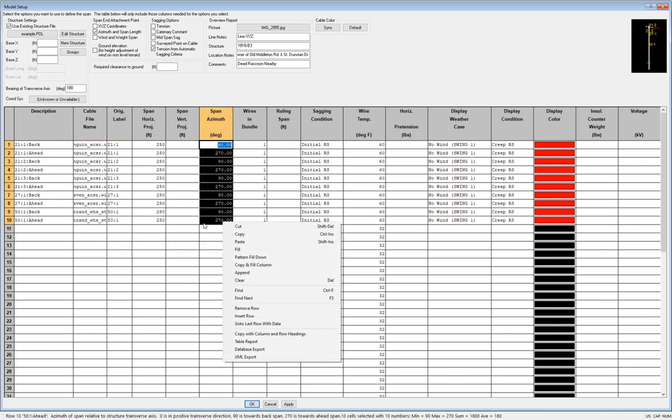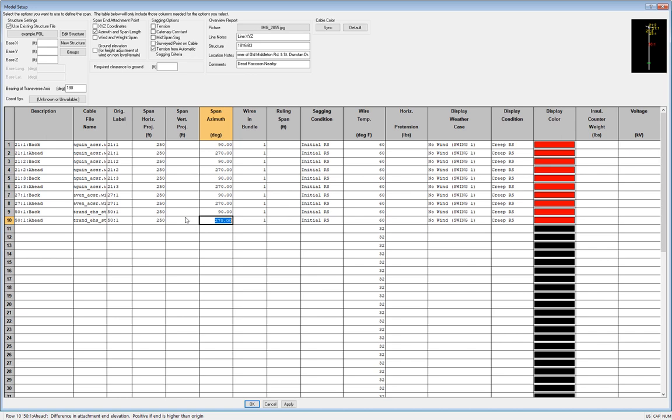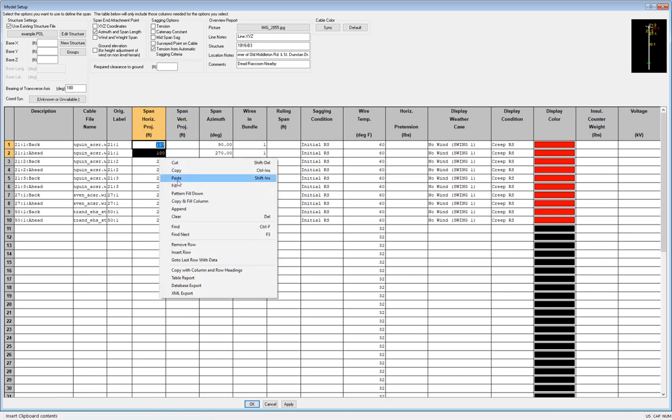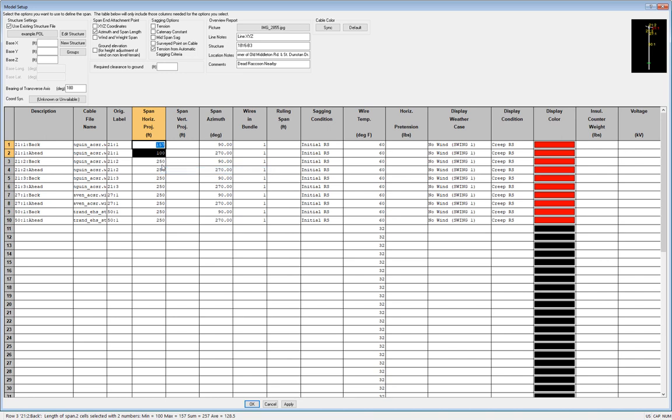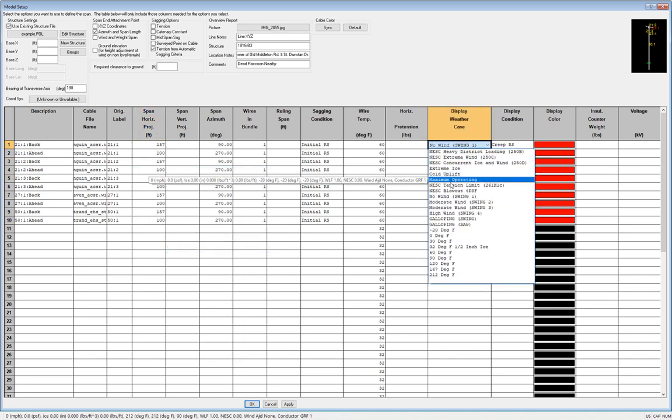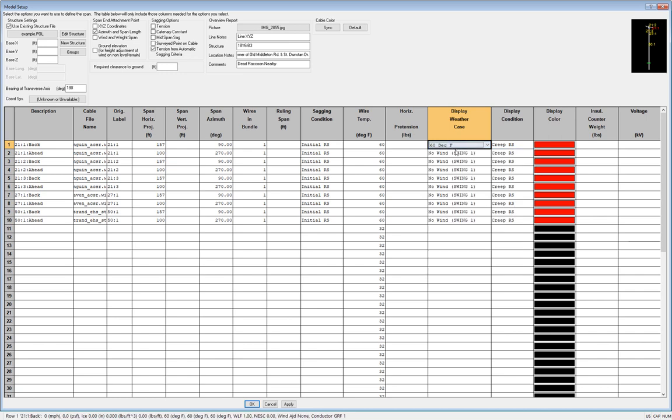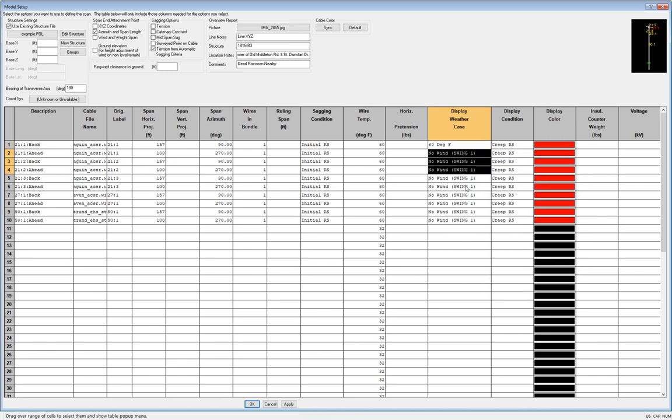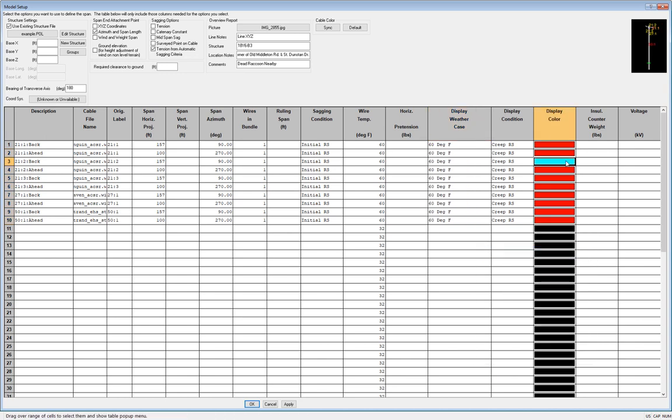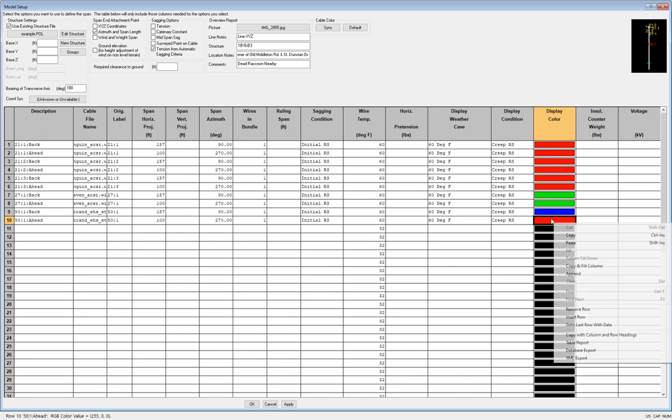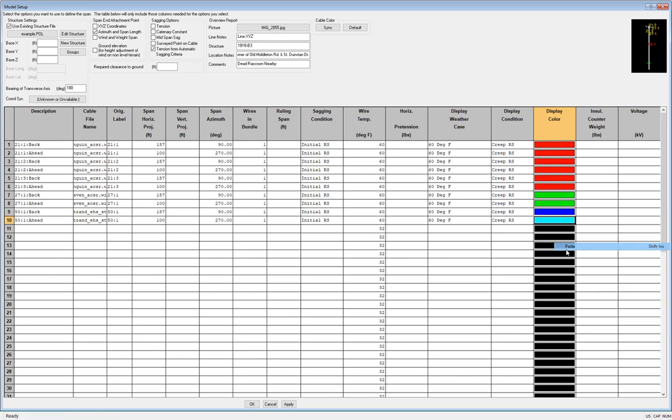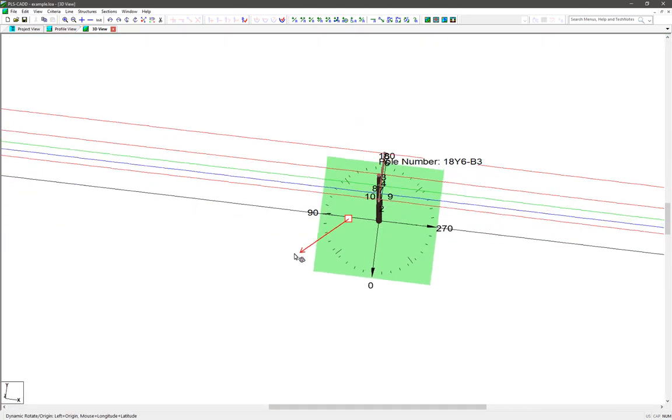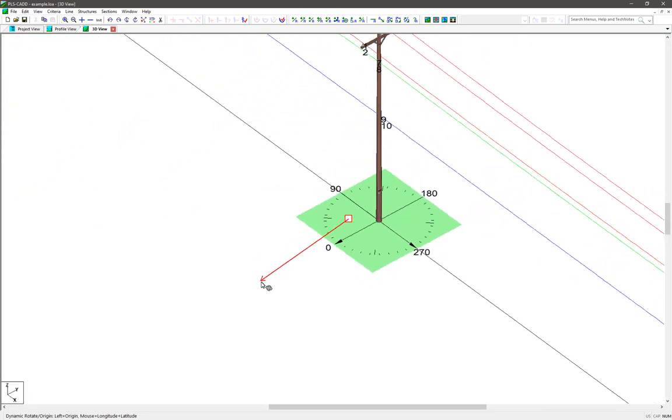The span azimuths, or wire direction, we don't need to make any changes to. The 270 degrees points to the head span, and the 90 degrees points to the back span. With this being a tangent structure, it doesn't need to be changed. We do, however, need to change our span lengths. The head span we measured to be about 100 feet, and the back span was about 157 feet. The only other things that we'll change here are the display conditions to just a simple 60 degree bare condition for the wire, and we'll color the wires differently so that we can tell them apart a little easier. Now we click OK, and we can see our pole in the 3D view, and rotate it all around to get a feel for it. It's almost ready to analyze.